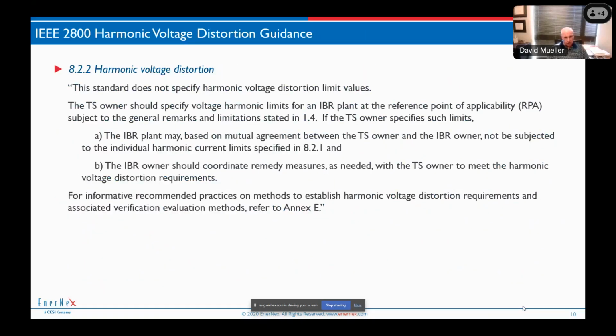What about harmonic voltage distortion? Well, first, the standard says this standard does not specify harmonic voltage distortion limit values, period. But then it goes on and it says the transmission system should specify voltage harmonic limits. So in other words, we're not going to set forward the limits in the standard, but the transmission system owner should set his limits, okay? And they should specify such limits. And then if they set the limits, we can talk about whether or not we want to even deal with the harmonic current limits, and we can talk about how we're going to remedy problems.